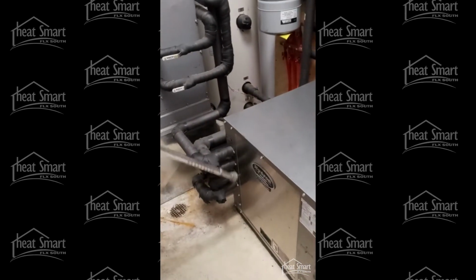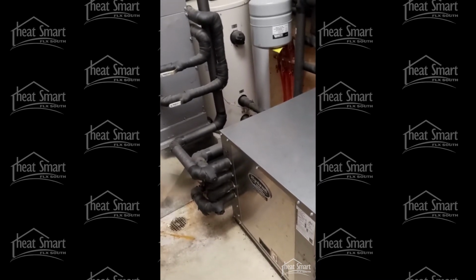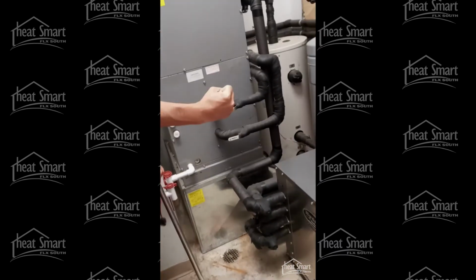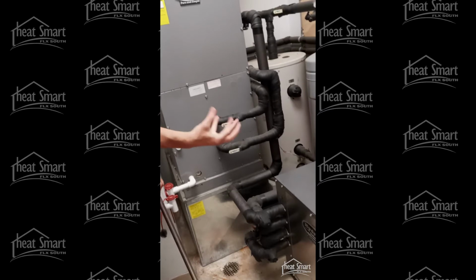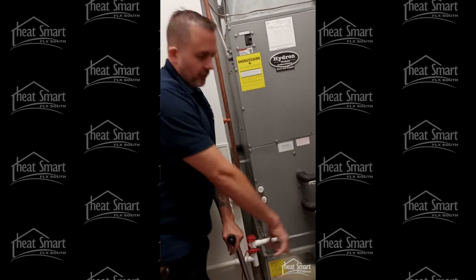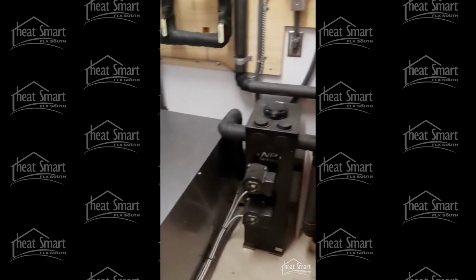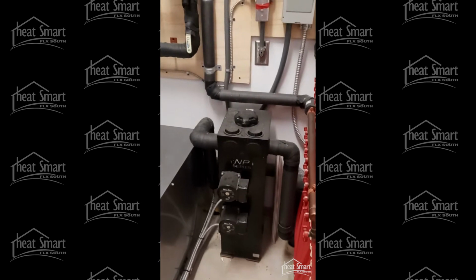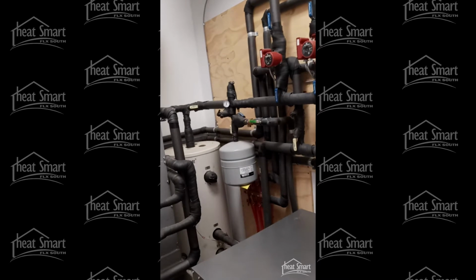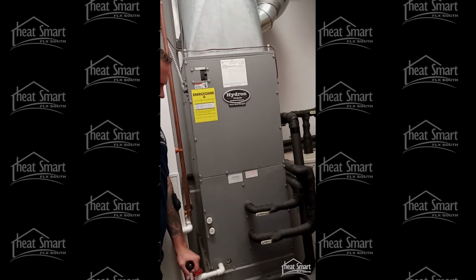So the heat pump, through the refrigeration cycle, runs that water over a coil and pulls the heat out with the refrigerant, and that refrigerant is where the heat is actually coming into the building. Then it discharges the colder water back into the loop to heat up again. Depending on how fast the system is running, that process can happen at up to 16 to 18 gallons per minute. A pretty high rate of flow.